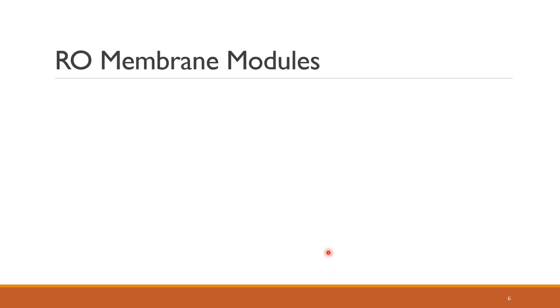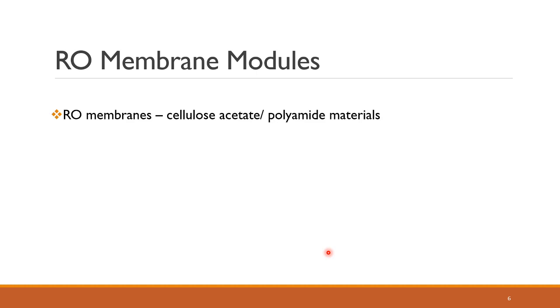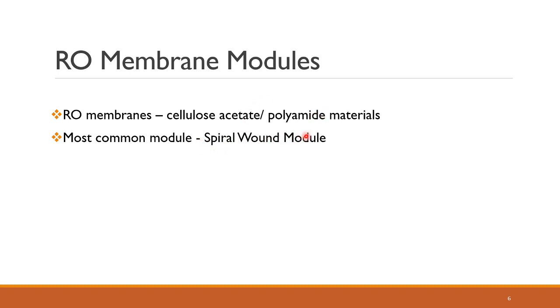Coming to RO membrane modules — you cannot use a single membrane for the process, you have to use multiple membranes arranged in modules. The reverse osmosis membranes are of two types, made from two materials: cellulose acetate and polyamide. These membranes are arranged in a spiral wound module, which is the most common arrangement, whereas the second and fairly uncommon type is called the hollow fiber or tubular membrane setup.